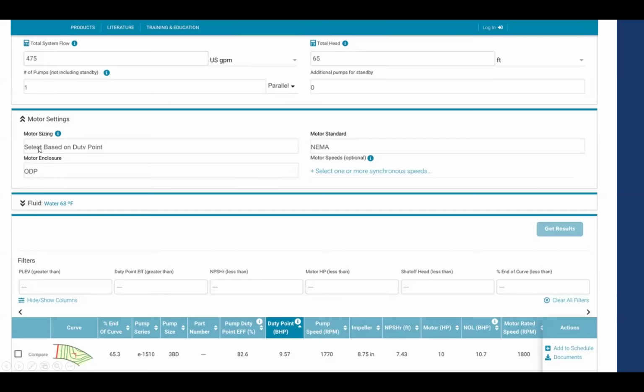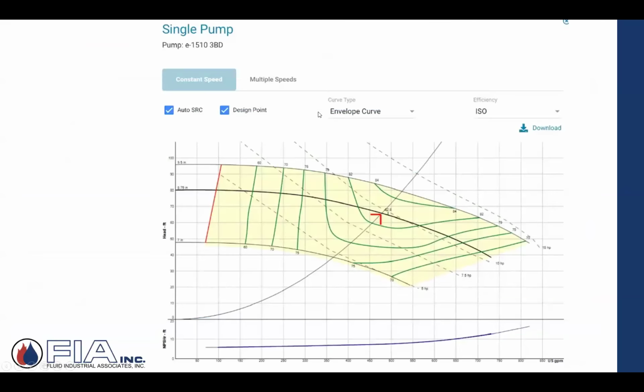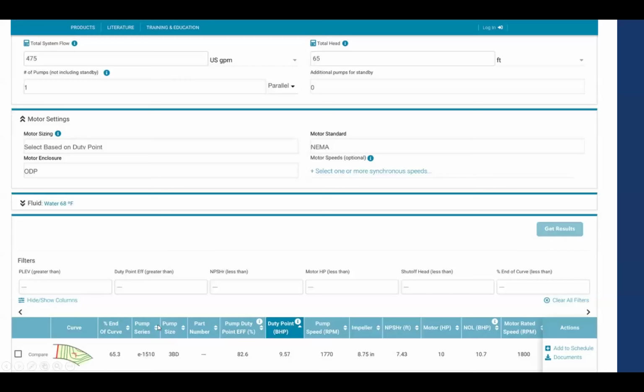Motor sizing, motor settings: select it based on duty point. Duty point means that flow at that feet of head. That's my very specific condition that I've calculated. So pick the pump accordingly. And when I do, here's the exploded pump curve with the system curve. I've got a control head here, so my system curve doesn't start down at 0, it starts at 20 feet. But what it's talking about here is at duty point, I'm not moving past that flow rate of 475 at 65 feet of head. And when I look at the required motor horsepower, it says 10 horsepower would be adequate. That'd be the proper horsepower at duty point.